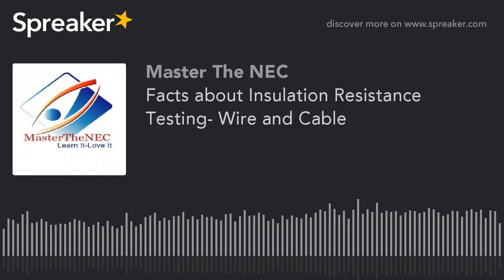Hopefully I've explained a little bit more to you about the testing and the condition, and I like to say it has to be what I call the perfect storm, the perfect test condition, in order to be able to test a cable. So as a summary, tray cable that's all non-metallic with all insulated conductors, even the equipment ground is insulated, is nearly impossible to do any type of test on, unless it's foil wrapped, unless it has some kind of aluminum type or foil around in intimate contact with the conductors.